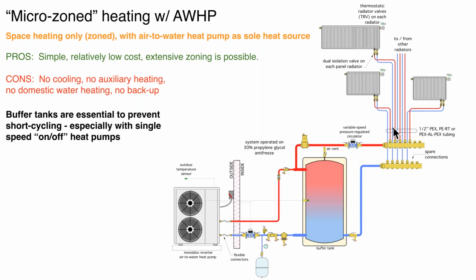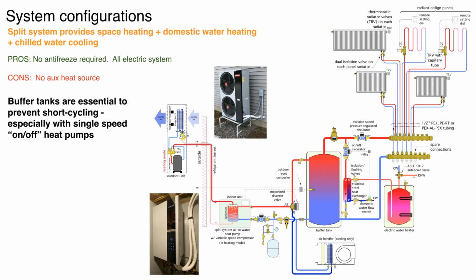All right. Now, I've taken that system and I've varied a little bit on this slide. This uses a split system air-to-water heat pump. And I'm doing this just to show you two different flavors of air-to-water heat pumps. The monoblock being a factory charge, everything is outside type of configuration. A split system is where we have an outdoor unit with a refrigerant line set that comes into an indoor unit. You can see the indoor unit down here on the wall. The nice thing about a split system is there's no water outside, so you're not required to put antifreeze in the system. The other thing I've added here is cooling, and we will talk about how can we add cooling in some of these commercial structures.